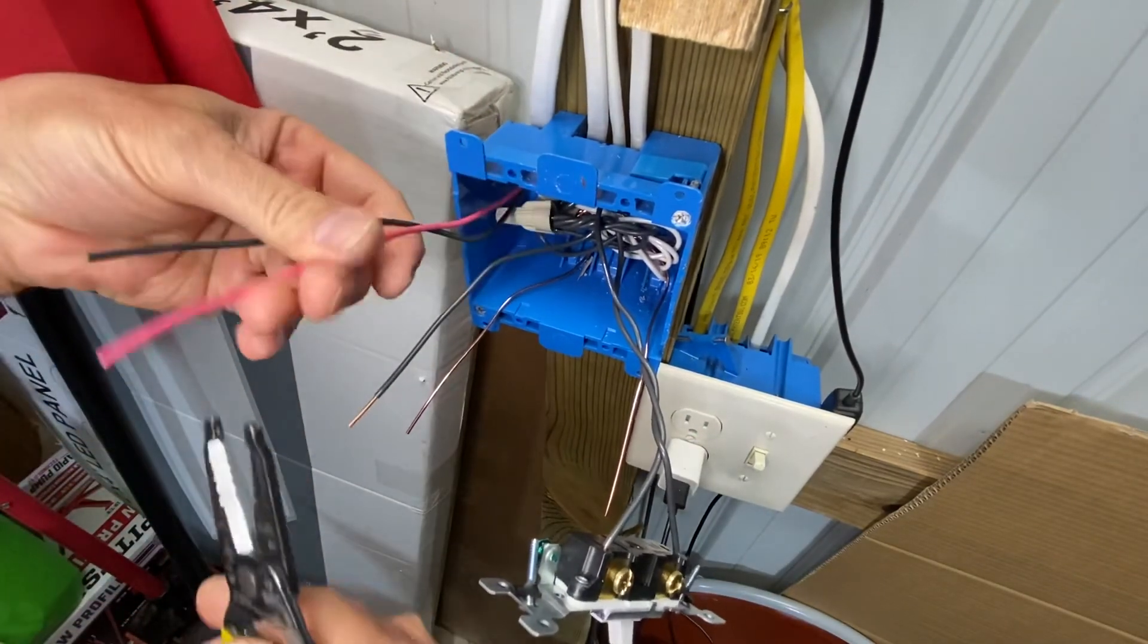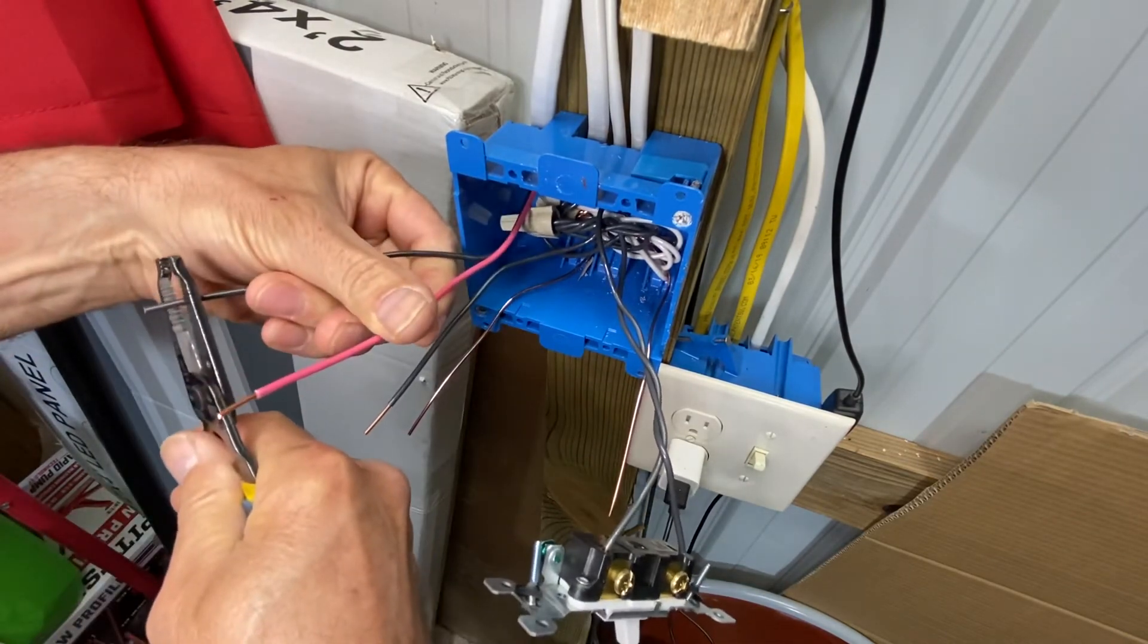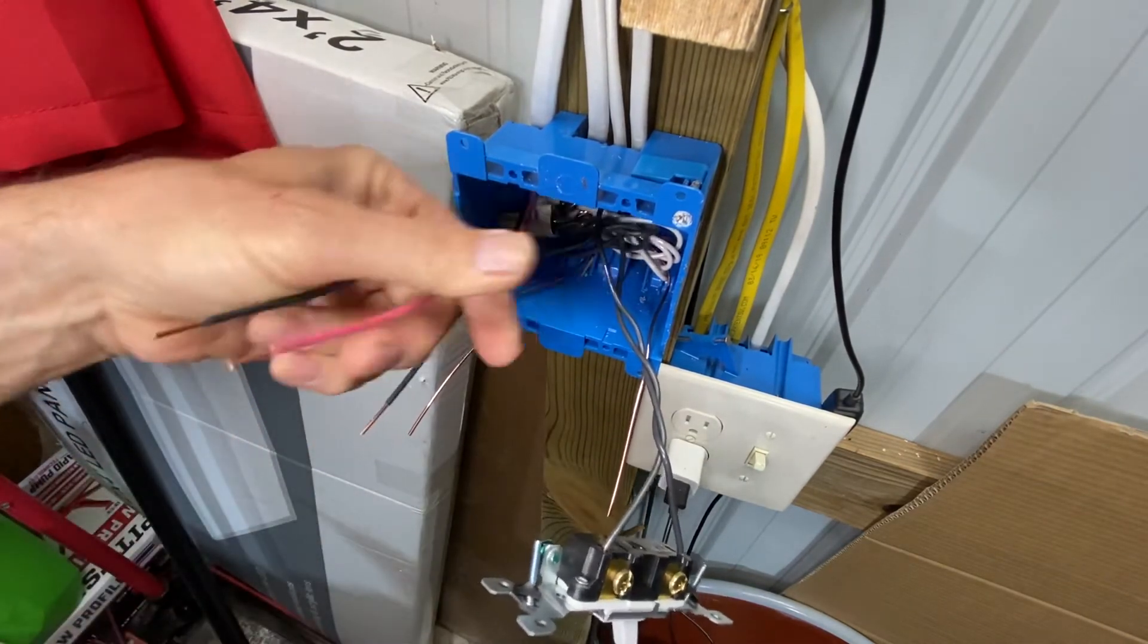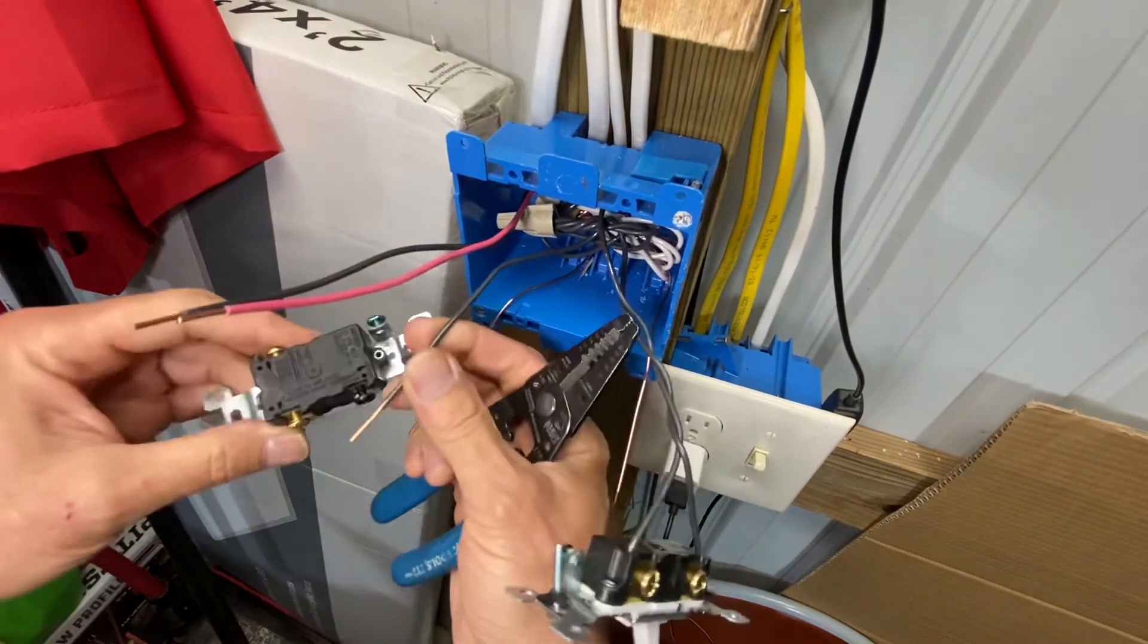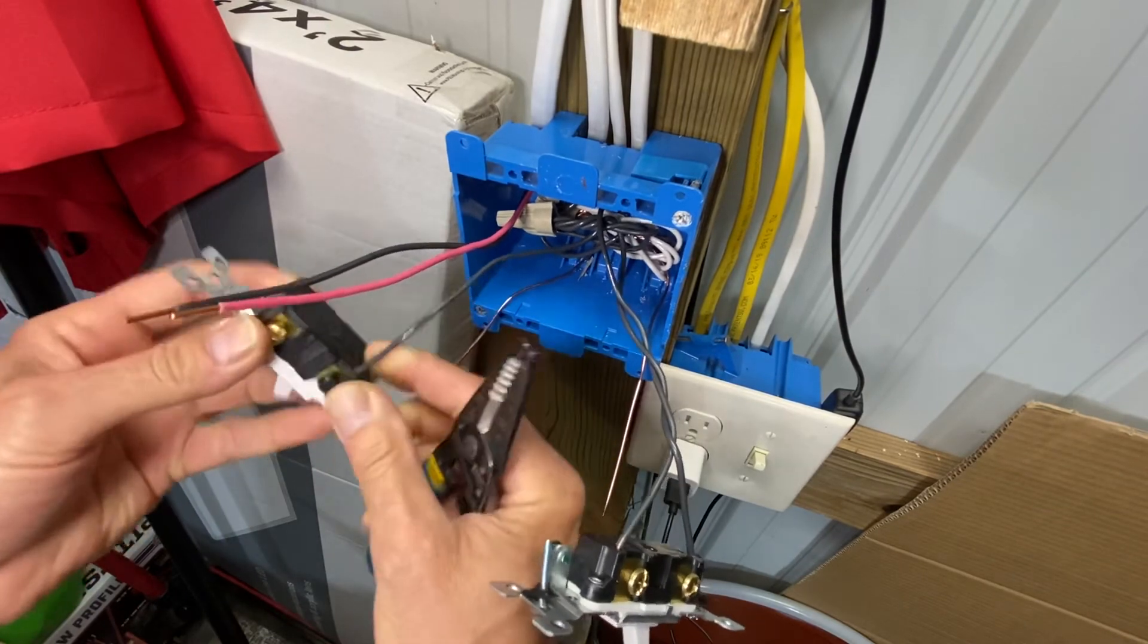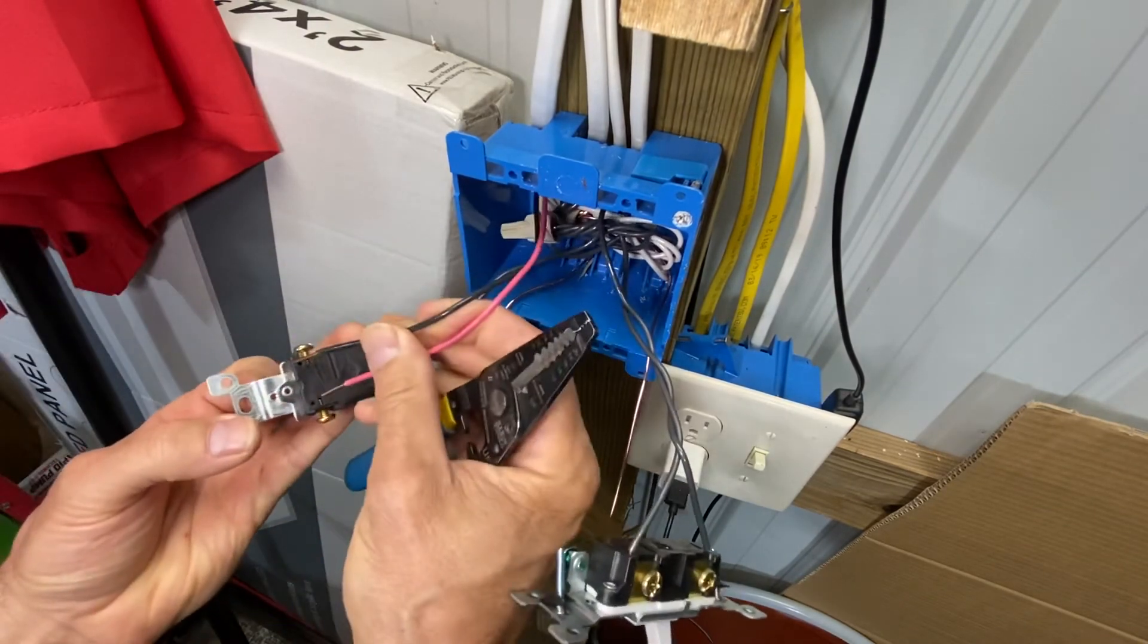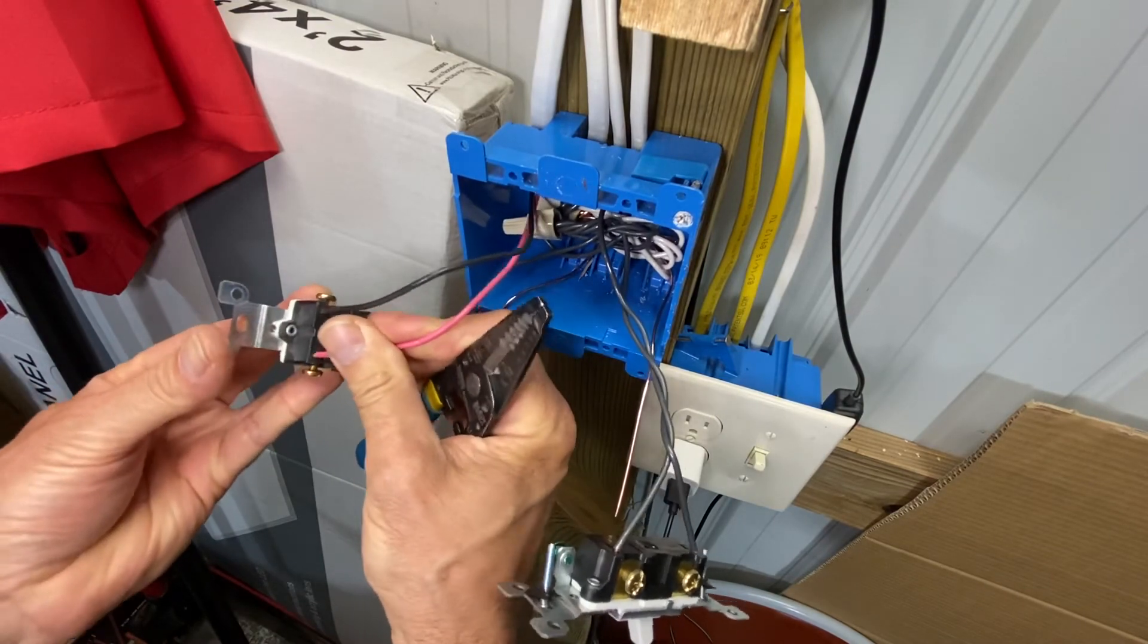Three wire. Three-way. Strip them off about a half an inch. Something. Now, the feed goes in the black screw. The travelers, it don't matter which side they go on. They can go in either way. Plug's in there. Give them a little twist.